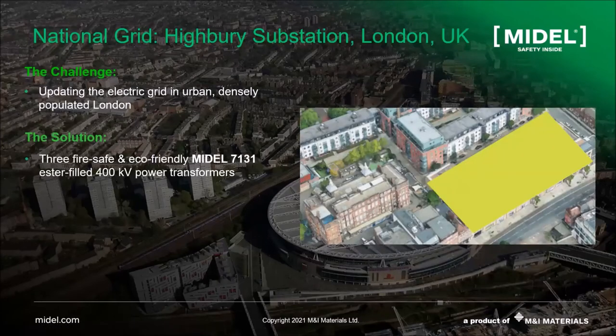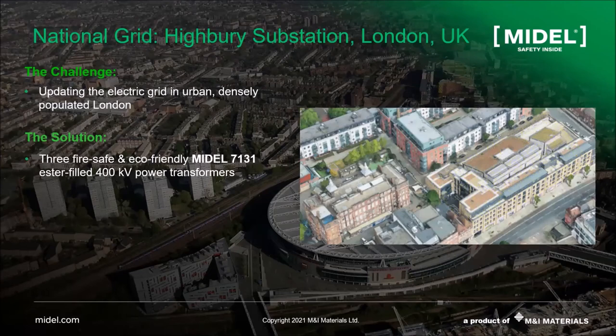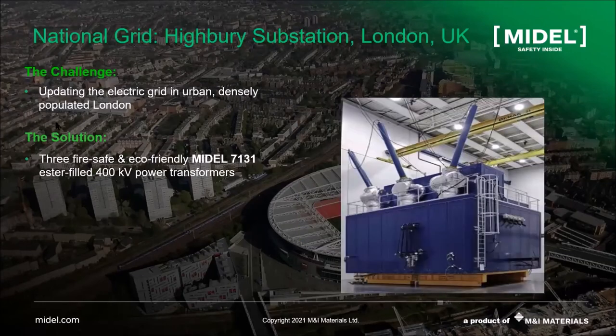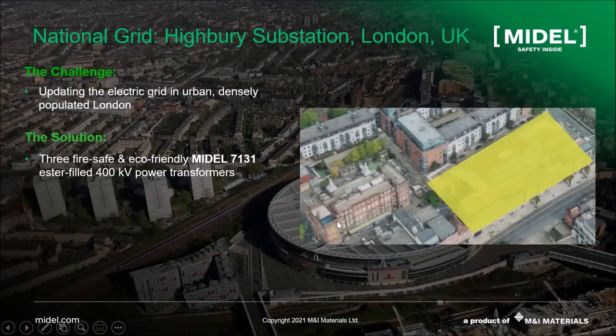And we went right past the transformer. The transformer is an interesting transformer in that it's got an outside cladding on it that allows it to collect waste heat, and that is then used to heat a school nearby. So it's a very innovative solution when designing the substation. You'll also see that the footprint in this yellow block took up the entire city block. The new substation with three transformers that were sized larger and more powerful were all MIDEL transformers, and they were able to take up a much smaller footprint.